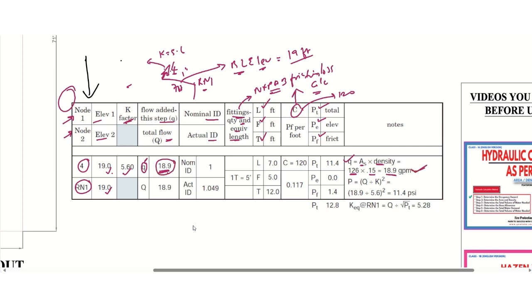The nominal ID of the pipe is 1 inch. The actual ID is 1.049 inches for black steel pipe. You can find this from any manufacturer data or NFPA 13 also mentions this.